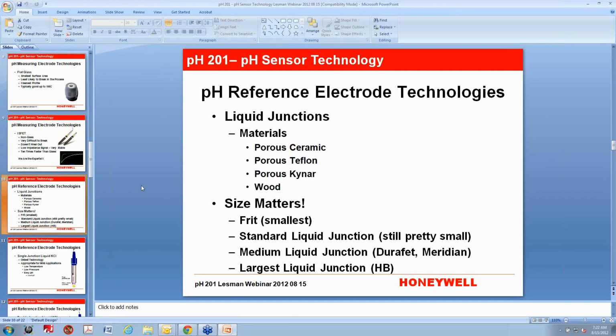That's a poisoning problem. Also, if the holes or the pores are too big, then that allows potassium chloride, depending on its formulation, to get sucked out of the reference area. And if you don't have the potassium chloride, you lose your electrical contact at the reference electrode. And of course, you're just surrounded by air, and so you don't have a stable voltage potential anymore around the reference electrode.